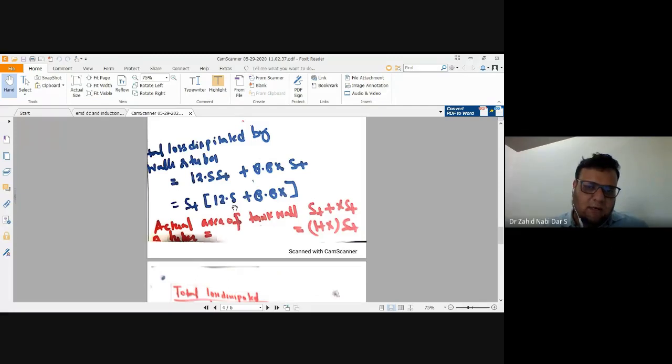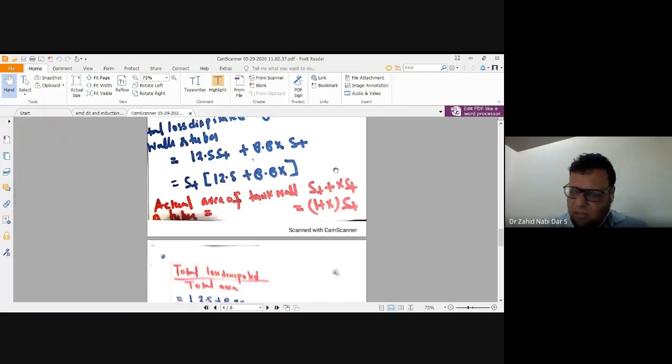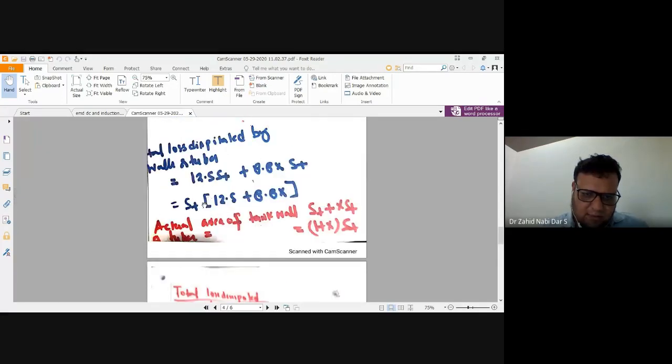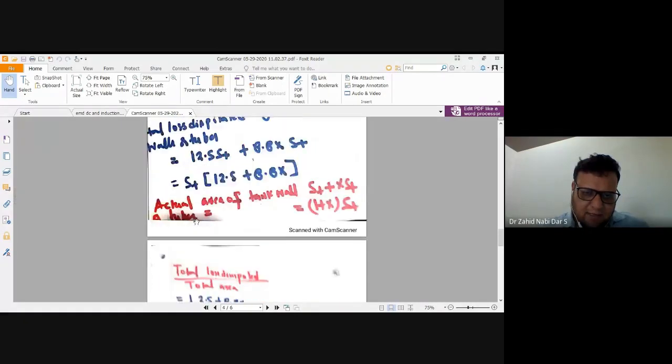So this is the total loss dissipated by wall tubes, 12.5 St plus 8.8 x St. For this, the derivation is there on the internet. Many people have viewed it. Our class strength is 46, and 400 people have viewed. Whether our class people have viewed or not, I made it very easy. In the books it's very complicated, so I studied 3 or 4 books and made it. So the actual area of tank wall with the tubes is (1 plus x) St. So the total loss dissipated would be St (12.5 plus 8.8x) divided by total area.